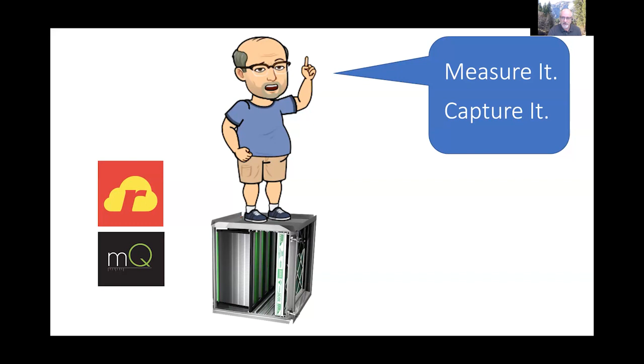The history of how bad these systems have been performing goes back as long as we've been able to document and keep track of it. Many of the reports I could show you were literally typed out on a typewriter. You can see the big stuff: at least one fault in 70 to 90% of homes, duct leakage in 90 to 100%, refrigerant charge and insufficient evaporator airflow issues. Airflow and refrigerant charge are really the only two things you can control, and they've been off for years because we don't measure them, and we usually don't measure them together. There are so many ways we've been able to document this, and it's costing homeowners billions of dollars.